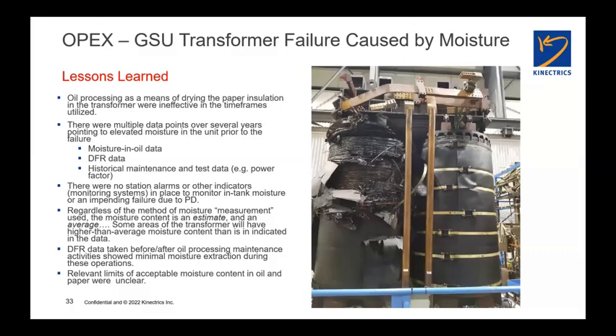So there's some lessons learned from this. I always tell folks, when you're looking at moisture content in a transformer, take a holistic approach. Don't just rely on the moisture in oil data. Do dielectric spectroscopy at a maintenance outage when the opportunity presents itself. Don't look at snapshot data at a point in time. Look at trends. When you're looking at DGA or oil test data, you always want to be looking at the trends. And be aware of the limitations of oil processing as a means to dry out transformers because of how we measure moisture content in a transformer.